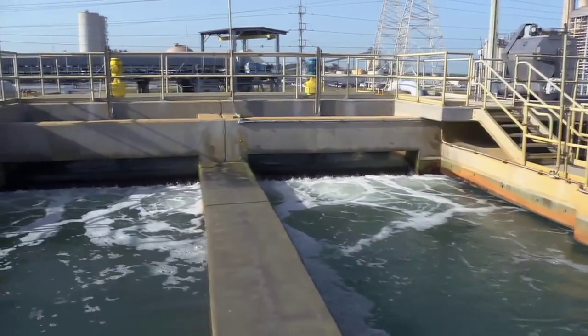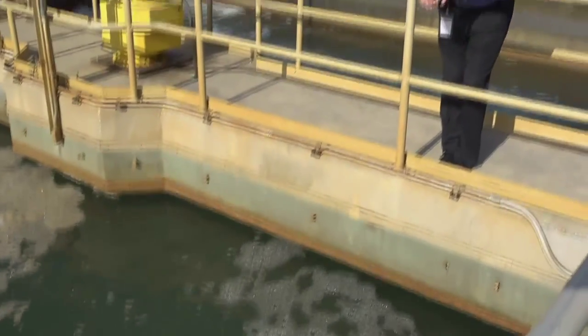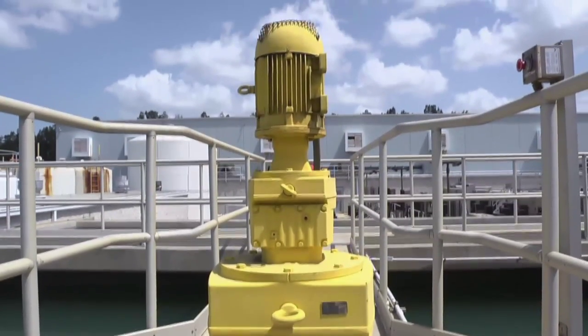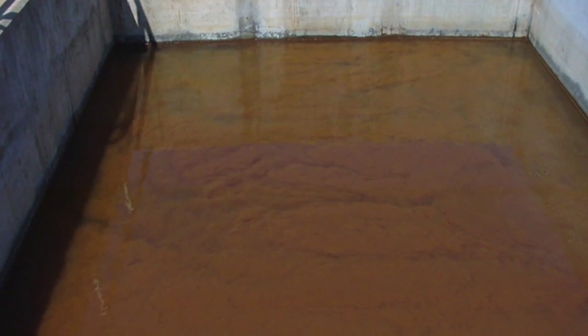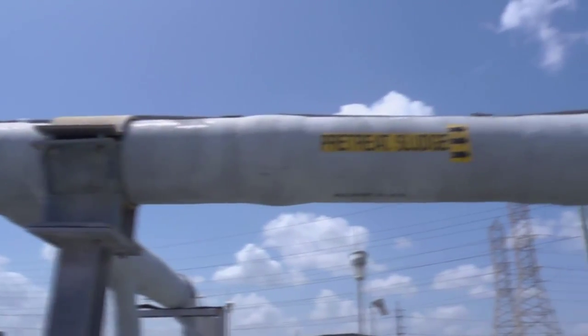The plant operates in multiple stages. First, the water goes through pre-treatment. We're adding some chemicals in order to get the smaller particles to stick together. The foam on top is proteins in the water — similar to the foaming action you see at the beach. The rust color comes from the coagulant we add, ferric chloride. Large fan blades stir everything up, getting the smaller particles to glue together, get heavier, and settle to the bottom. Large chains pull boards every 10 feet apart, dragging settled material to pumps that remove the waste.